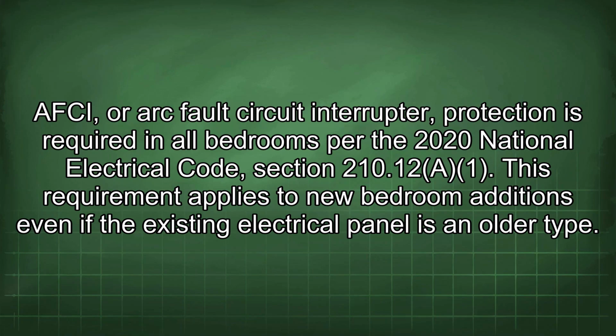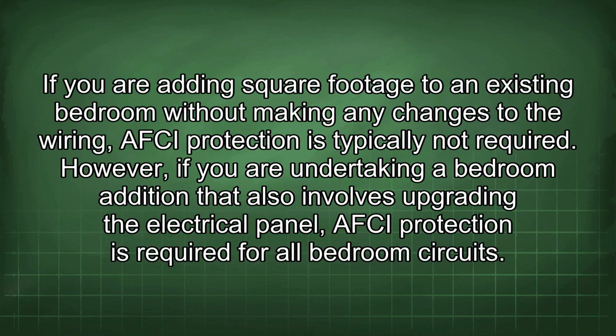AFCI, or arc fault circuit interrupter, protection is required in all bedrooms per the 2020 National Electrical Code, Section 210.12(A). This requirement applies to new bedroom additions even if the existing electrical panel is an older type. If you are adding square footage to an existing bedroom without making any changes to the wiring, AFCI protection is typically not required. However, if you are undertaking a bedroom addition that also involves upgrading the electrical panel, AFCI protection is required for all bedroom circuits.